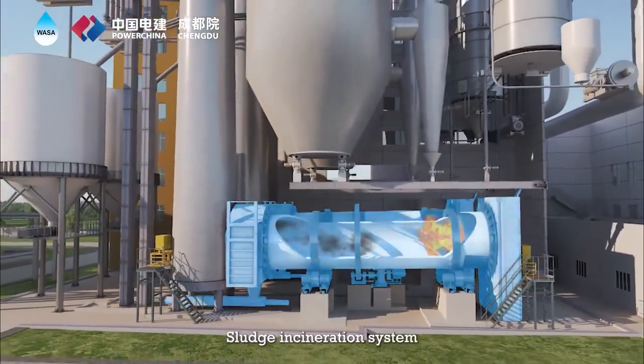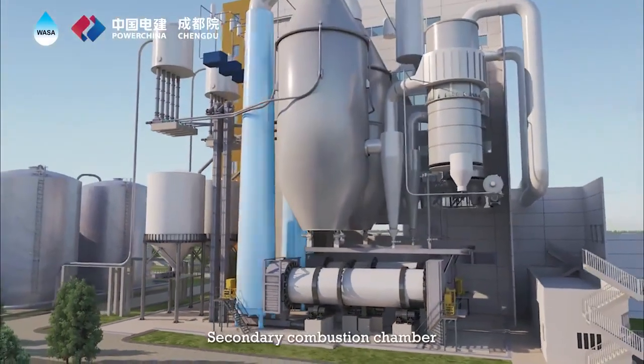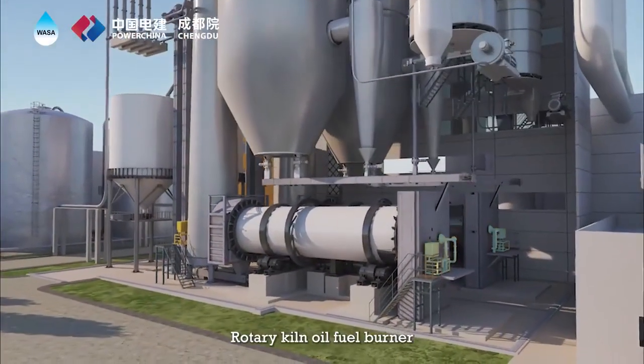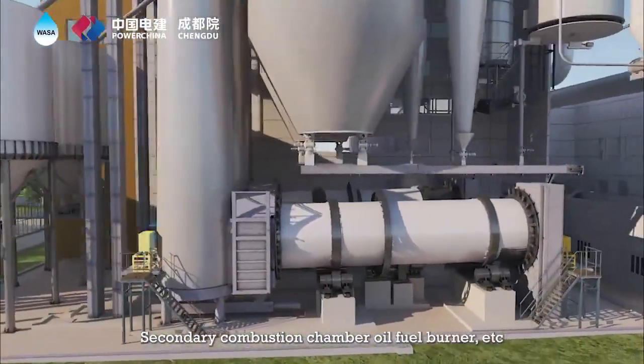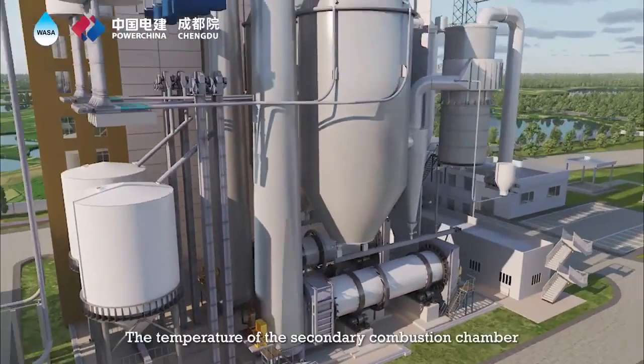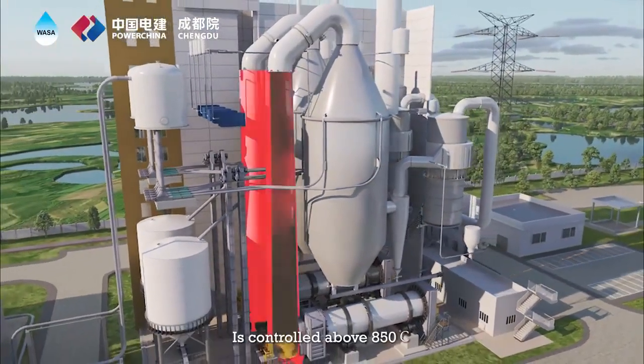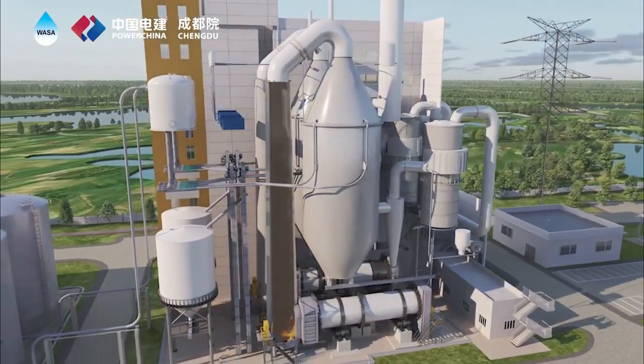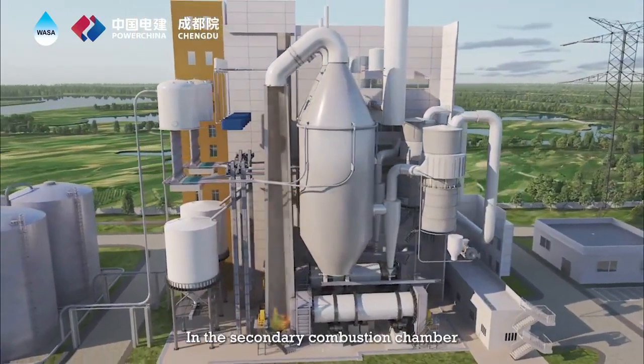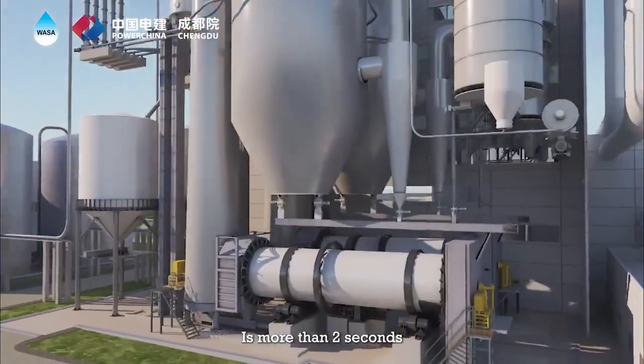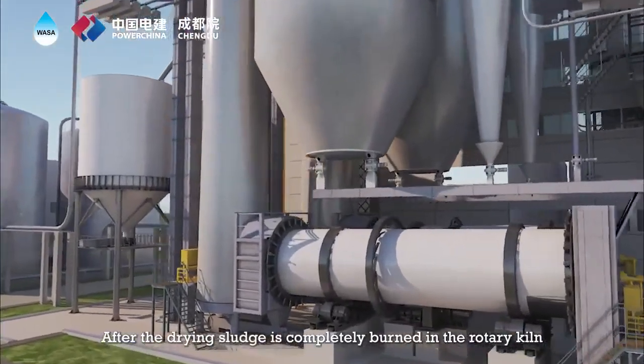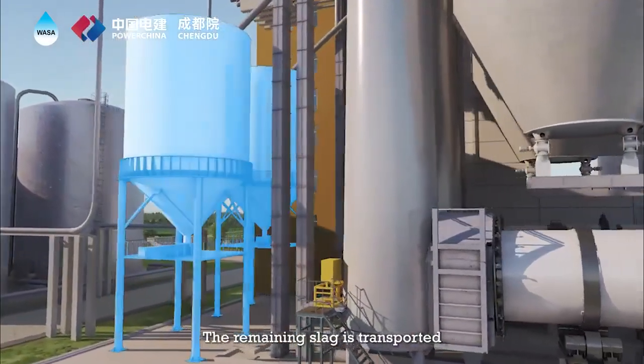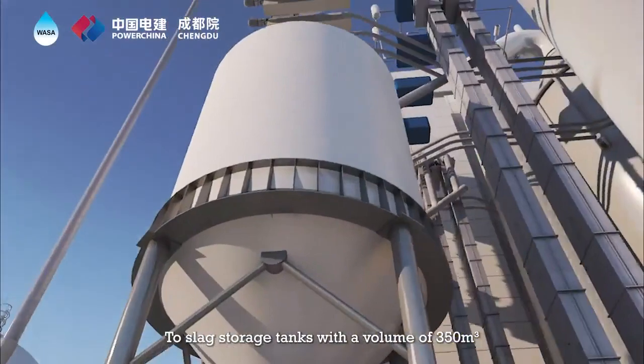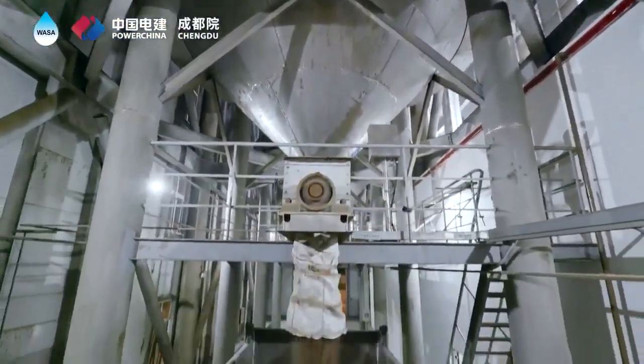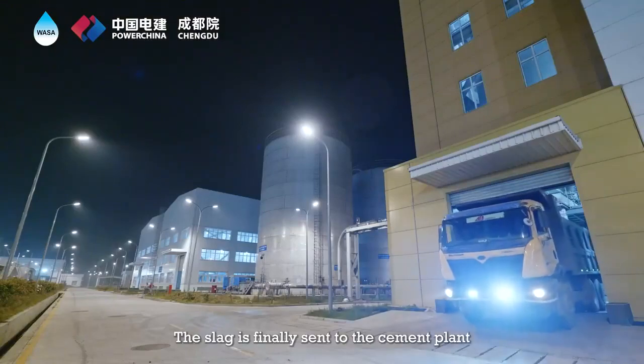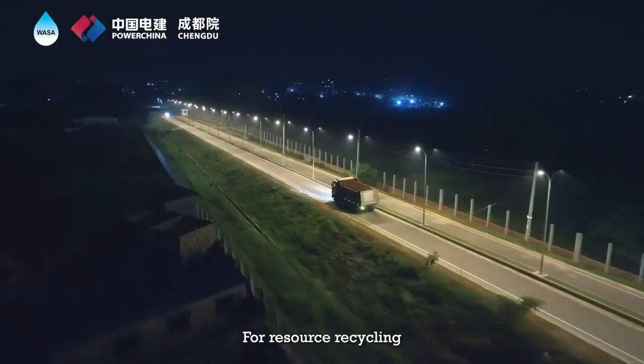The sludge incineration system consists of a rotary kiln, secondary combustion chamber, rotary kiln oil fuel burner, secondary combustion chamber oil fuel burner, etc. The temperature of the secondary combustion chamber is controlled above 850 degrees Celsius, and the residence time of the flue gas in the secondary combustion chamber is more than 2 seconds. After the dried sludge is completely burned in the rotary kiln, the remaining slag is transported to slag storage tanks with a volume of 350 cubic meters. The slag is finally sent to the cement plant for resource recycling.